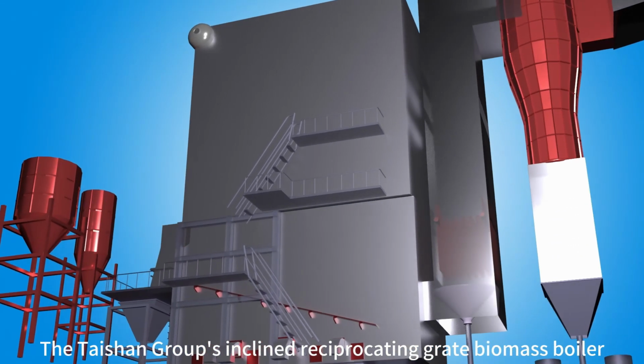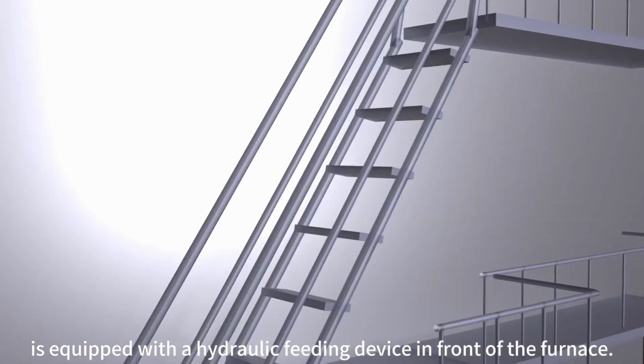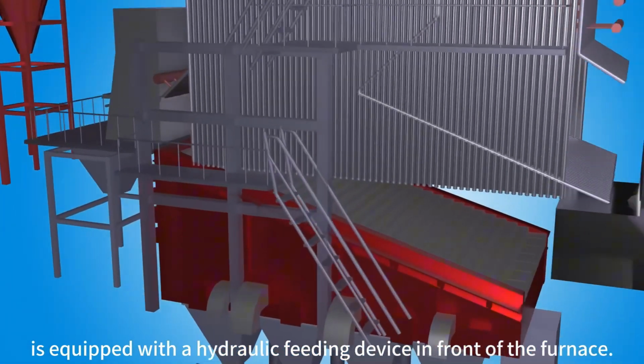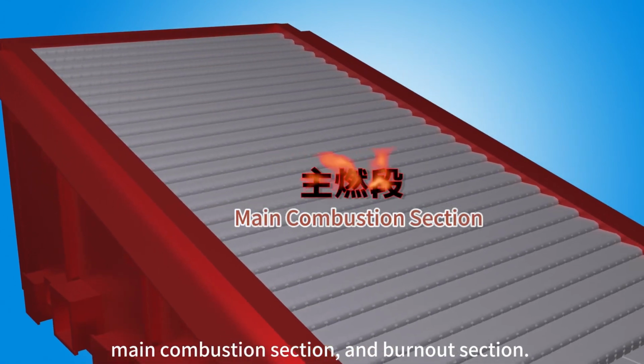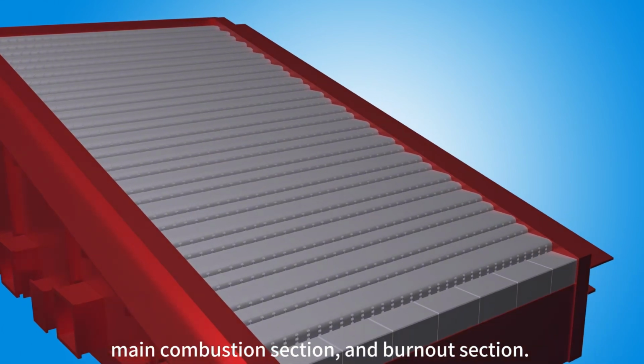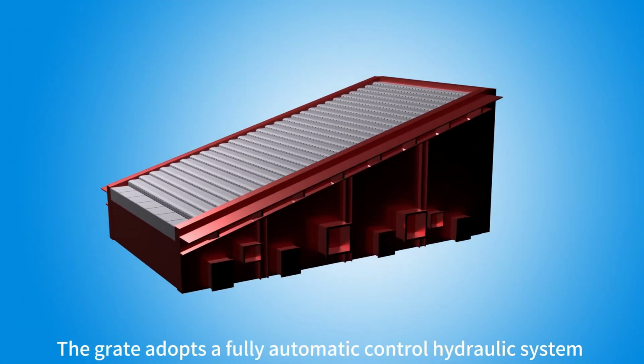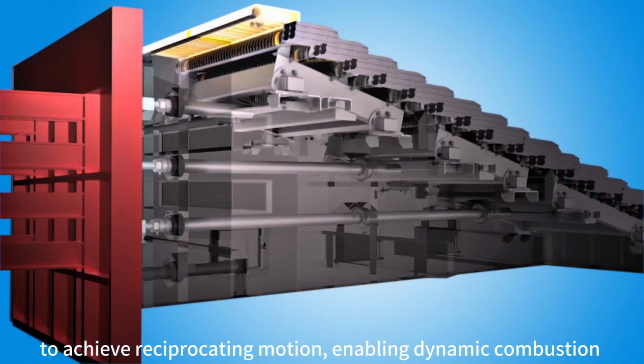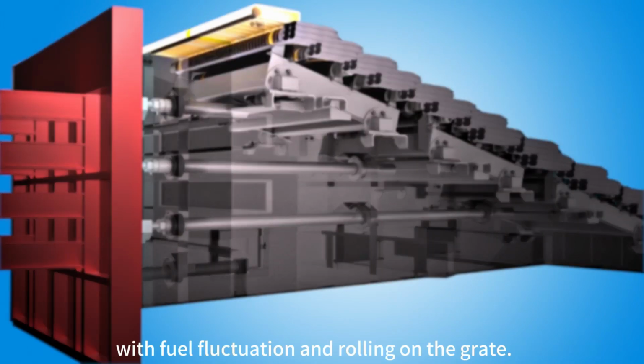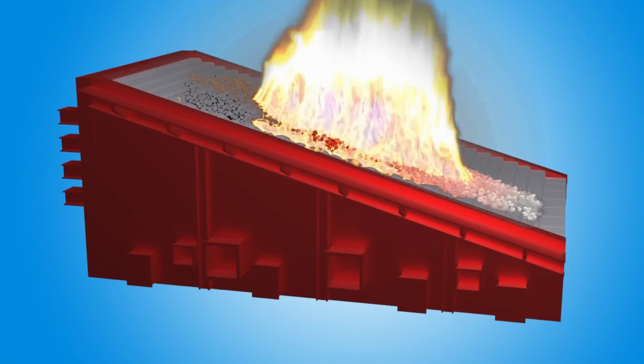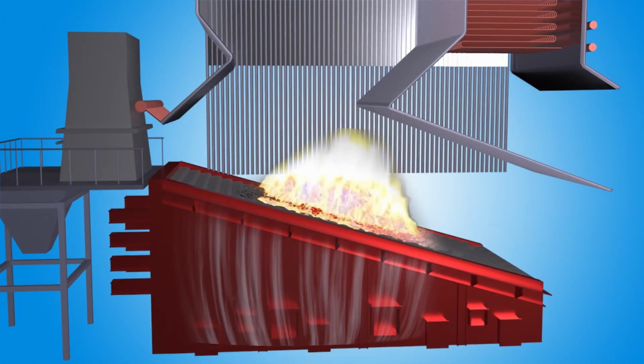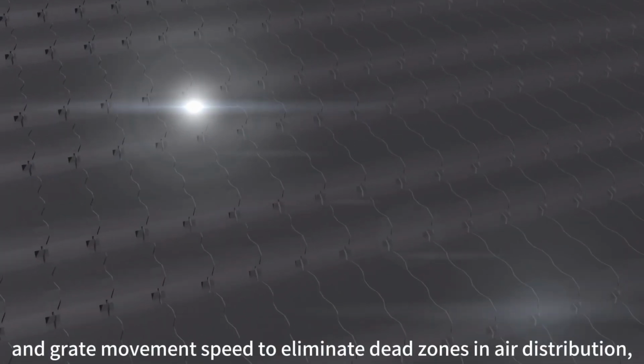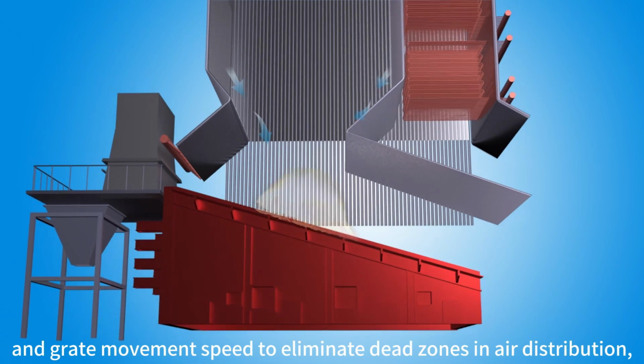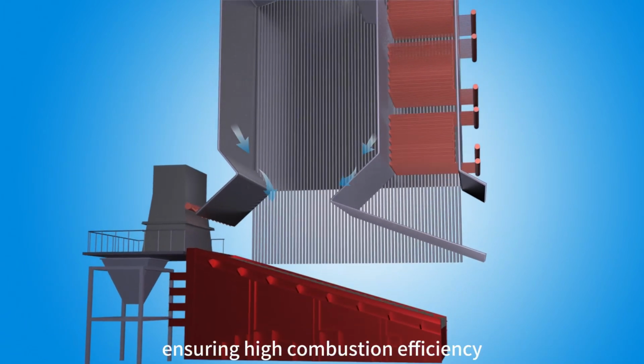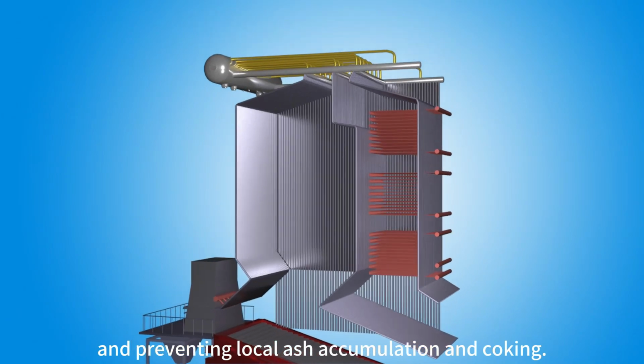The Taishan Group's inclined reciprocating grate biomass boiler is equipped with a hydraulic feeding device in front of the furnace. The grate is generally divided into a drying section, main combustion section, and burnout section. The grate adopts a fully automatic controlled hydraulic system to achieve reciprocating motion, enabling dynamic combustion with fuel fluctuation and rolling on the grate. Each combustion section is equipped with a reasonable air distribution ratio and grate movement speed to eliminate dead zones in air distribution, ensuring high combustion efficiency, and preventing local ash accumulation and coking.